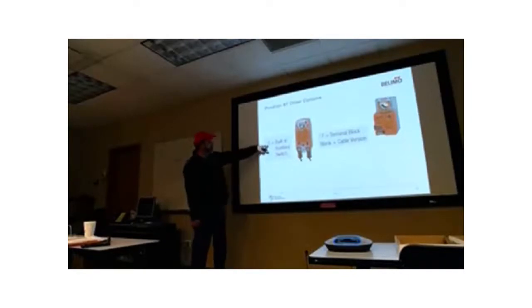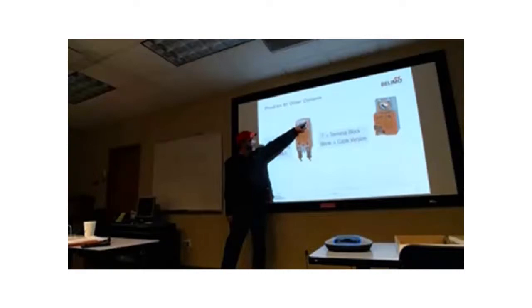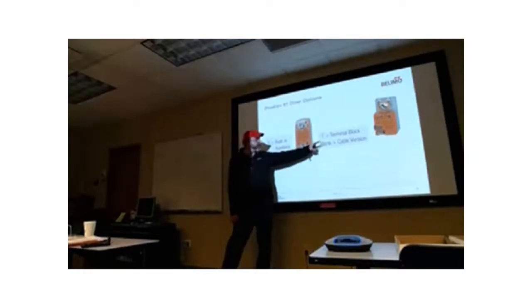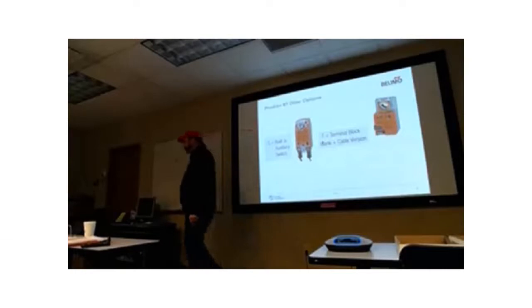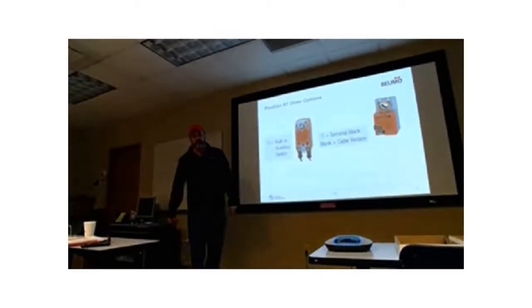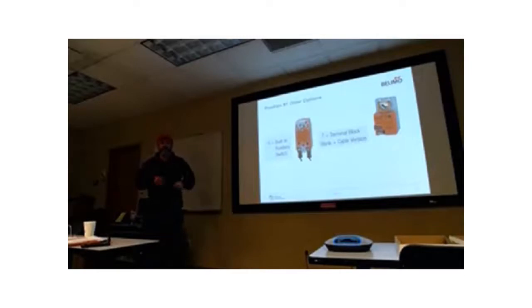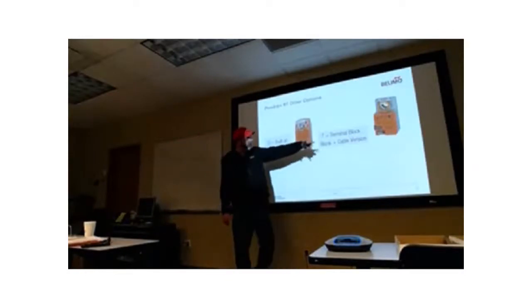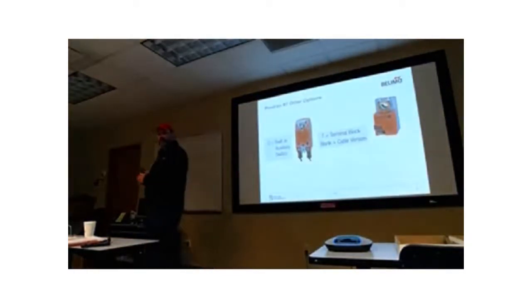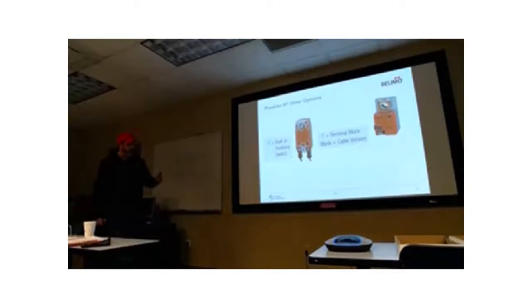So we make a -S, built right into our actuators, up here in the corner. On our non-spring return actuators, we make a -T, which is a terminal block. Instead of a cable whip like this, we have a terminal block and you can wire directly to the actuator. You don't have to go to a junction box, and sometimes that's advantageous. You can wire straight through. For this particular actuator, we have a little cover you can put on to finish it off, rather than having the cable whip hanging out flapping in the breeze.